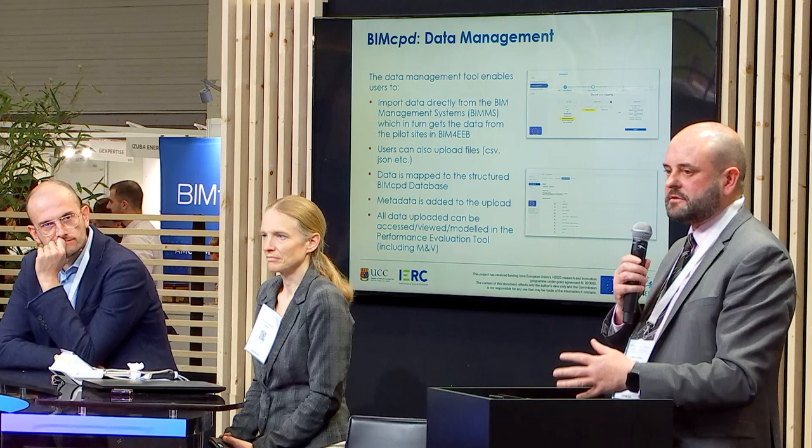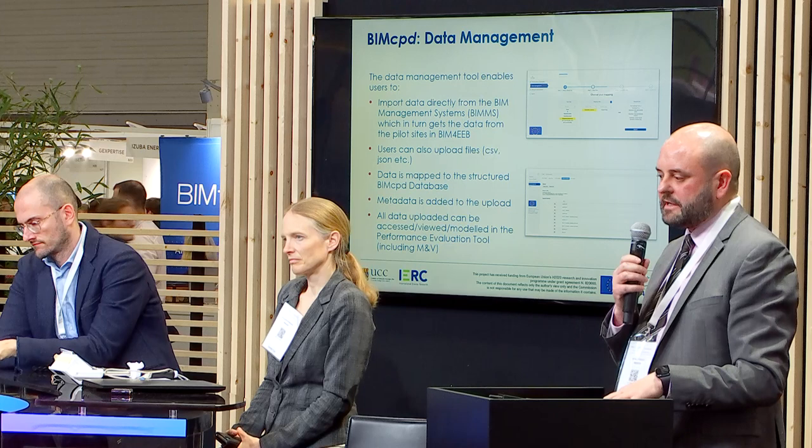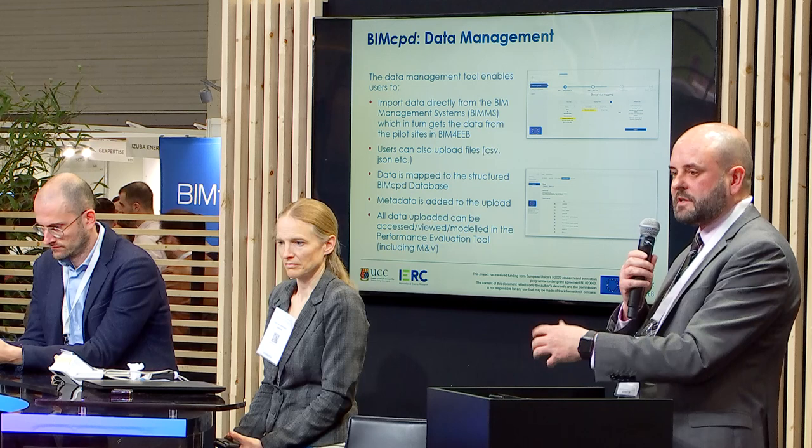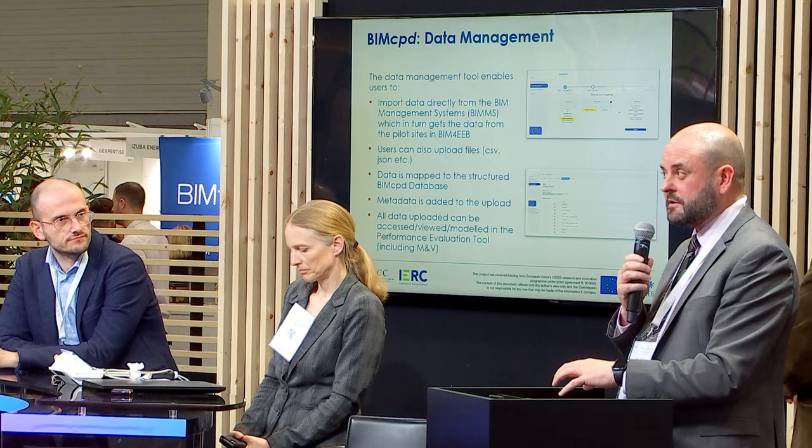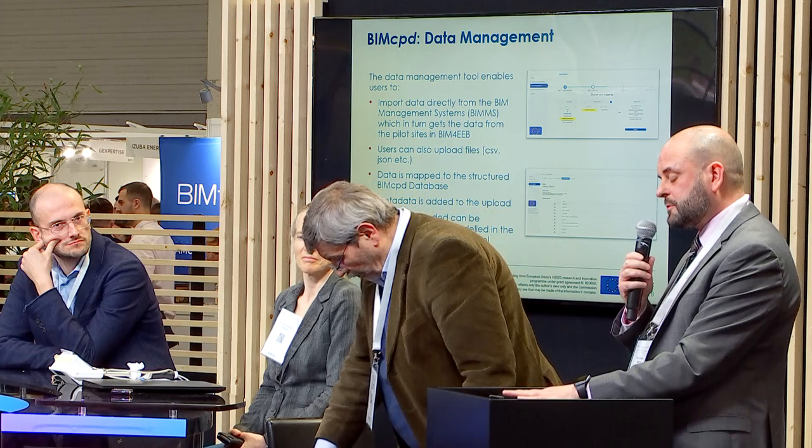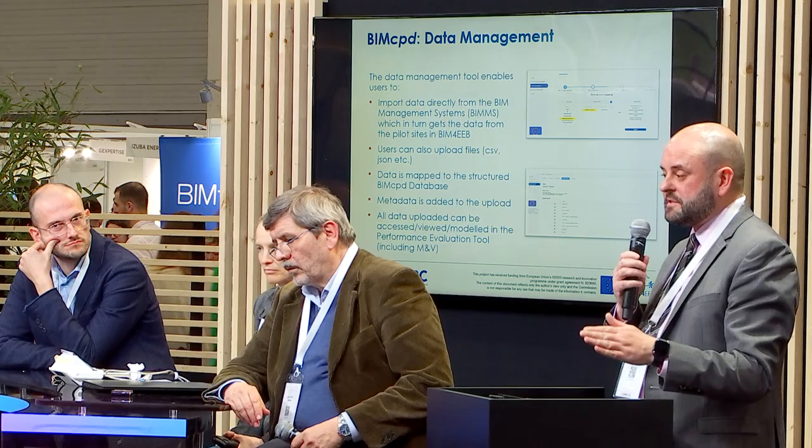So whether you were importing directly by uploading data into BIMCPD, or connecting to the BIM Management System and importing via SPARQL, via API, you could basically map that data source to our structured database, which was based on Project Haystack, but also the EU Open Building Stock Observatory. Once we had that structure in place of what we want the data to look like in the end, we were able to map that from the source to the structured database, which made the performance evaluation much more accurate, because everything was using the same units.